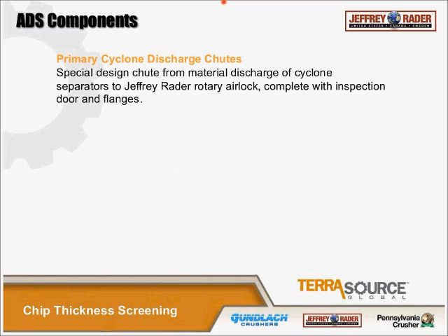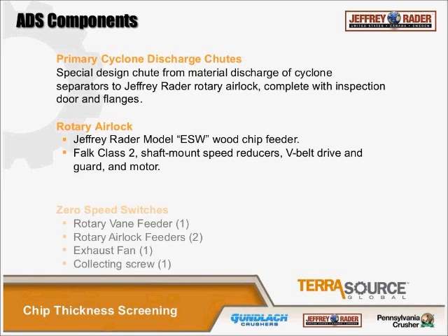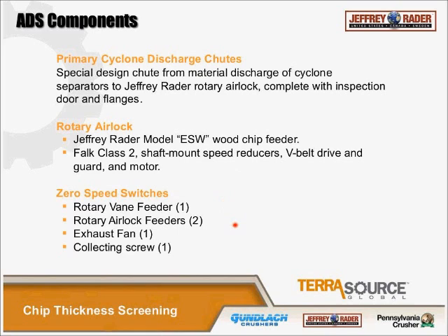The operation of the system depends on differential pressure across the cyclone, which is measured and monitored through a control panel to open or close the damper on the fan to optimize performance. Underneath the cyclone there's a discharge chute specially designed to break the vortex going through the cyclone so chips fall out and don't get carried back up into the top. This feeds into a typical ESW-type wood chip feeder used in pneumatic systems. The system usually has zero-speed switches for the rotary vane feeder, infeed zone, rotary airlock feeders, exhaust fan, and the screw feeding the ADS system.